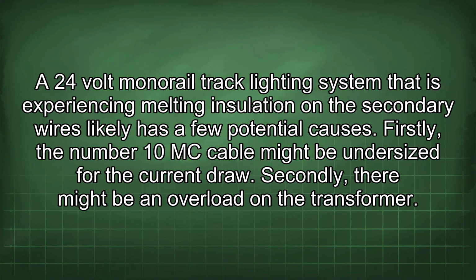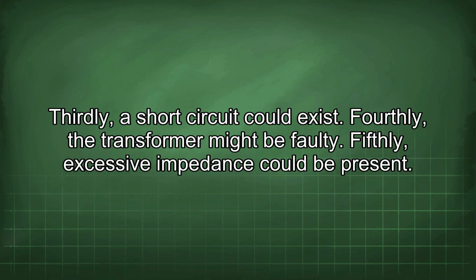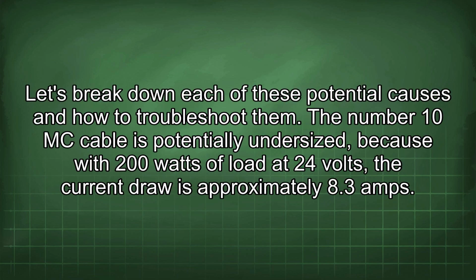A 24-volt monorail track lighting system that is experiencing melting insulation on the secondary wires likely has a few potential causes. Firstly, the number 10 MC cable might be undersized for the current draw. Secondly, there might be an overload on the transformer. Thirdly, a short circuit could exist. Fourthly, the transformer might be faulty. Fifthly, excessive impedance could be present. Let's break down each of these potential causes and how to troubleshoot them.